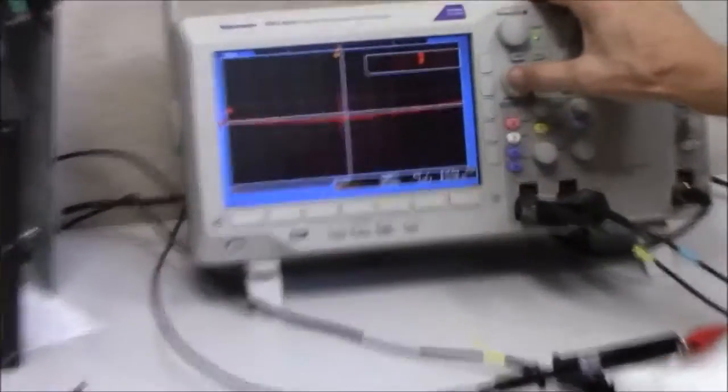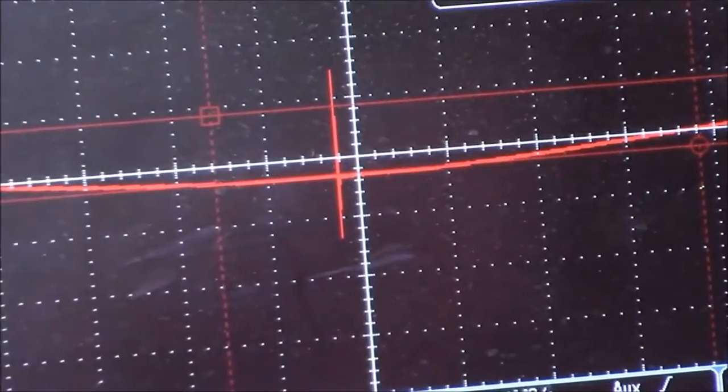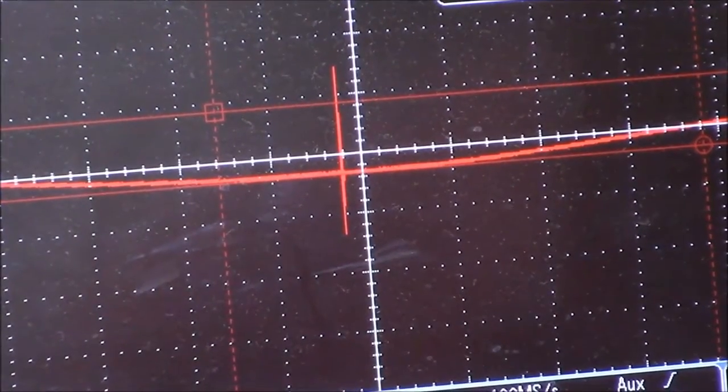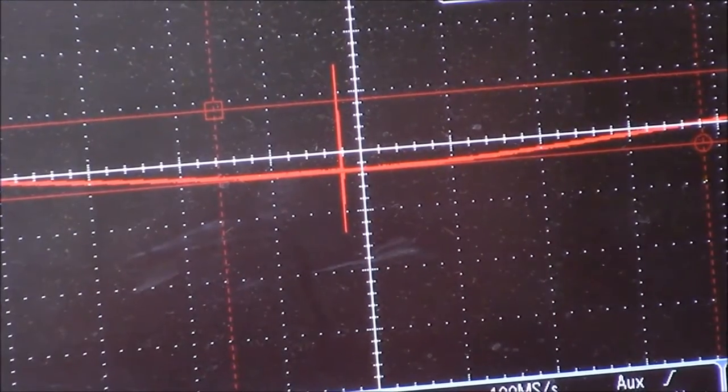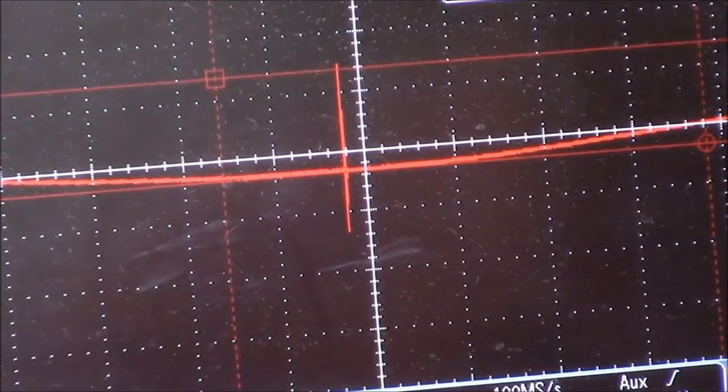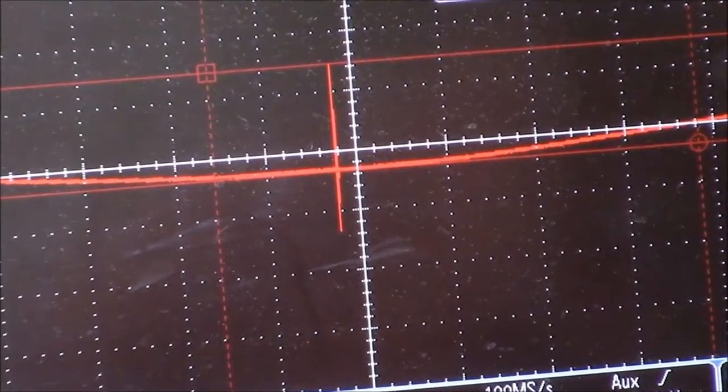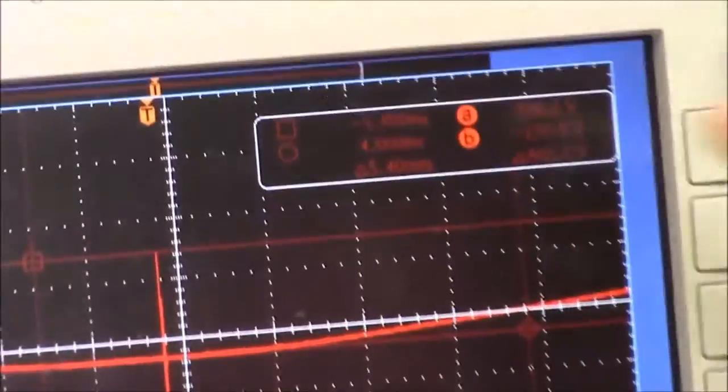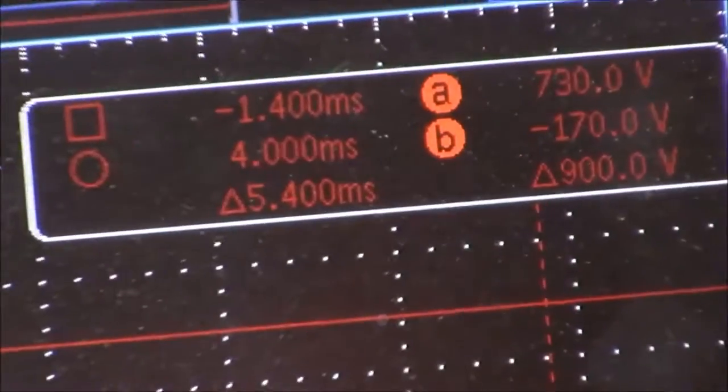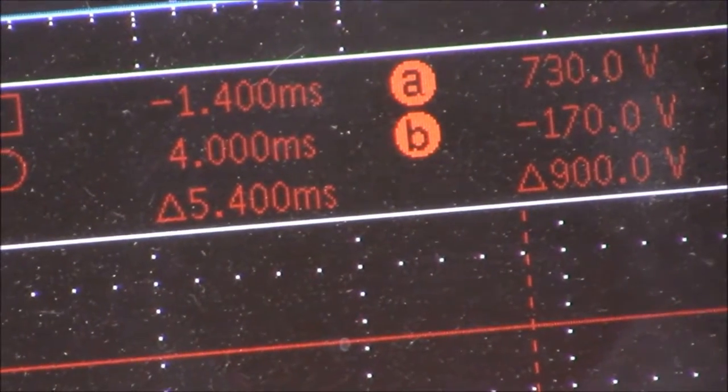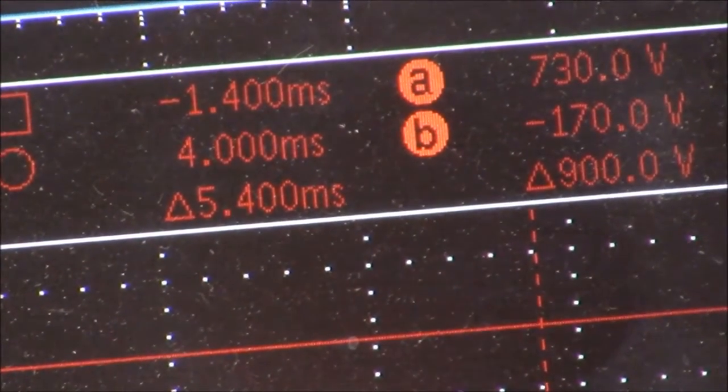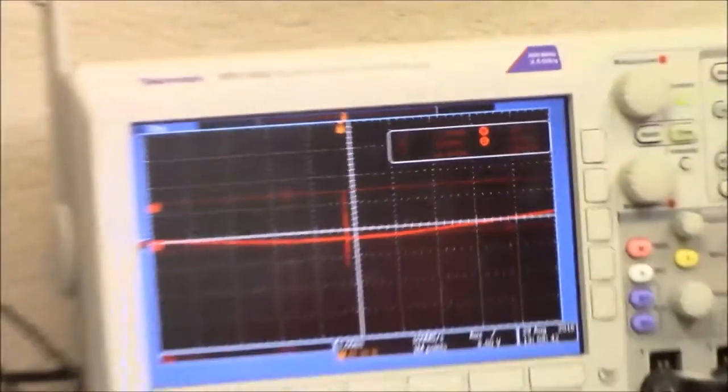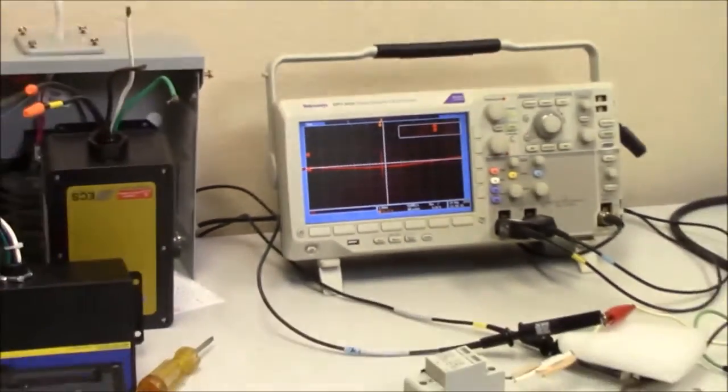Okay, here with these red lines we'll get down to the base of the sine wave. We'll inject it at 270 degrees and with the top cursor we'll measure the top, and this unit here has a residual or let through voltage of 900 volts. So with respect to protecting electronics, it's not really going to do a very decent job of removing or eliminating false zero crossings.